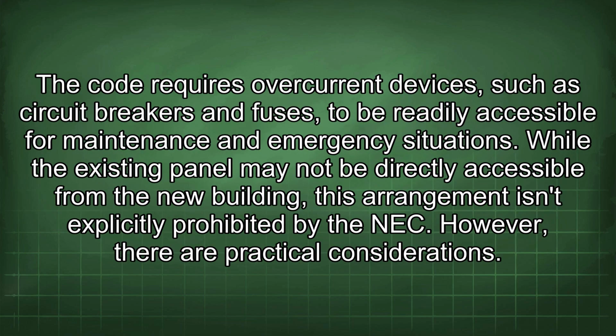premises. The code requires overcurrent devices, such as circuit breakers and fuses, to be readily accessible for maintenance and emergency situations. While the existing panel may not be directly accessible from the new building, this arrangement isn't explicitly prohibited by the NEC. However, there are practical considerations.